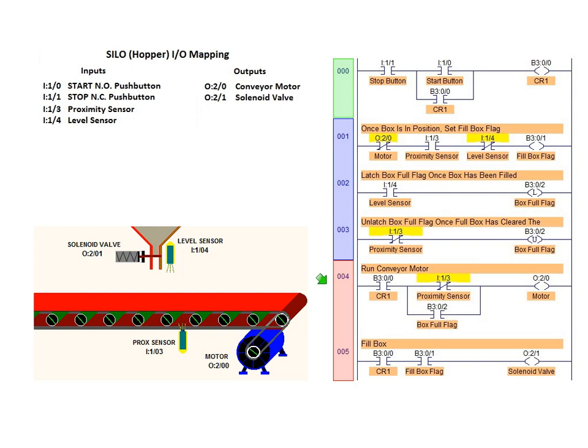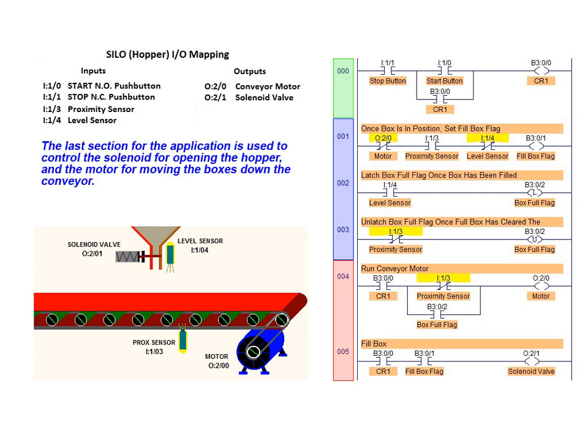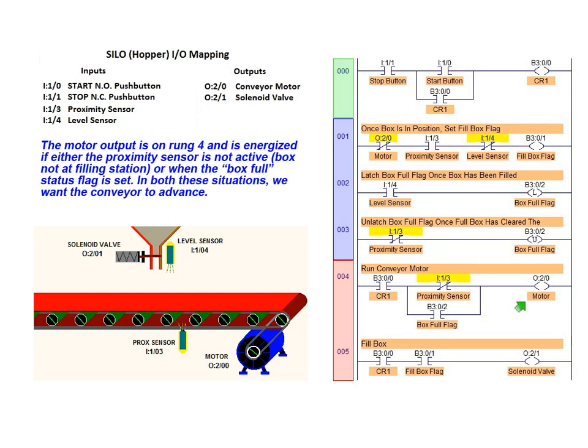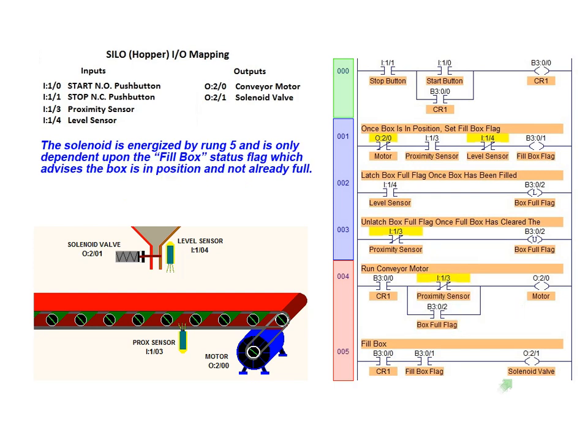The last section of the silo program consists of two rungs which are used to control the outputs of the application. One rung controls the conveyor motor, which brings boxes to and carries boxes from the filling station. The other output rung controls the solenoid valve. We have included B3 0.0 contacts on each of these output rungs to ensure that continuity is interrupted if the seal-in circuit is broken, which would occur when the stop button is pushed. The motor output on rung 4 is energized if either the proximity sensor is not active or if the box full status flag is set. The solenoid is energized by rung 5 and is only dependent upon the fill box status flag, which advises when the box is in position and not already full.